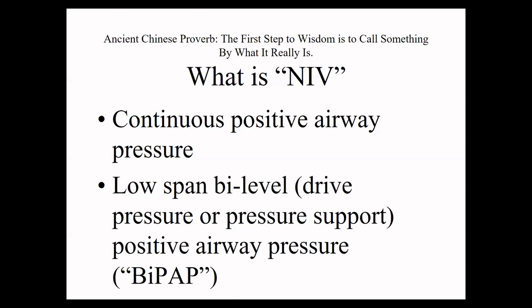Now, bi-level PAP can be helpful if you give a good span. So in other words, if I get hit by a truck and become a C1 quadriplegic, if I have no muscles below my neck at all, zero, I have 0 milliliters of vital capacity. Now, vital capacity is the volume of the deepest breath you can take. If it's 0, it means you can't breathe at all. It means you don't have any muscles to breathe with at all. So let's say that my vital capacity is 0. Now, to give me a breath to keep me alive, I would need either 600 milliliters of air, which would create a pressure of 18 centimeters of water in my lung, or you could give me a pressure of 18 centimeters of water, which would give me about 600 milliliters in my lungs. So whether you set a machine to deliver volume or pressure, the end result is basically the same. You could provide full ventilatory support by giving a pressure of about 18 centimeters of water or the volume that would create.